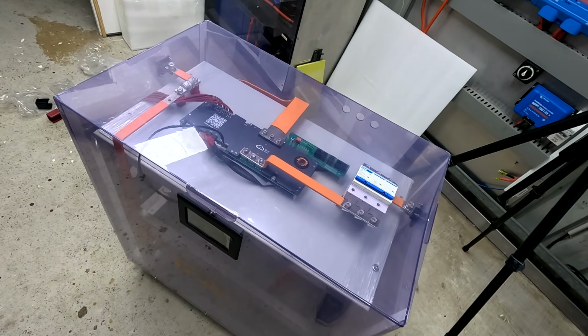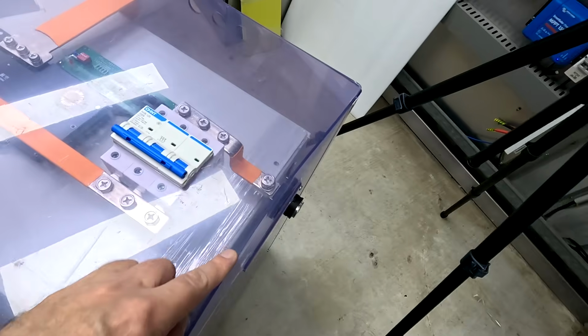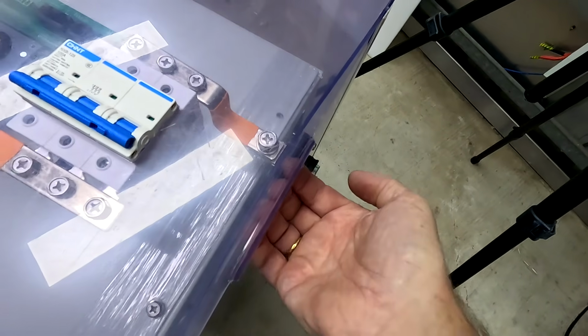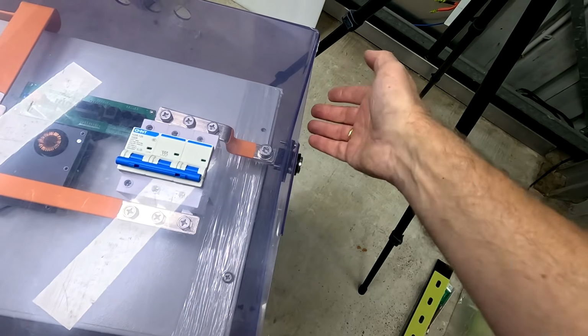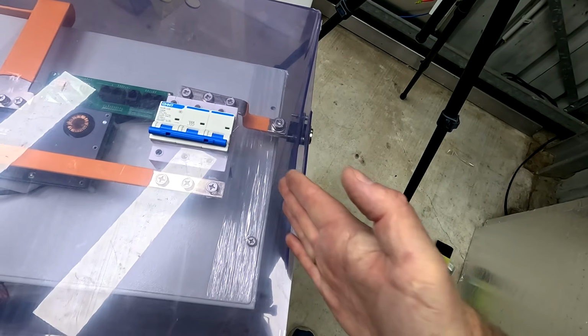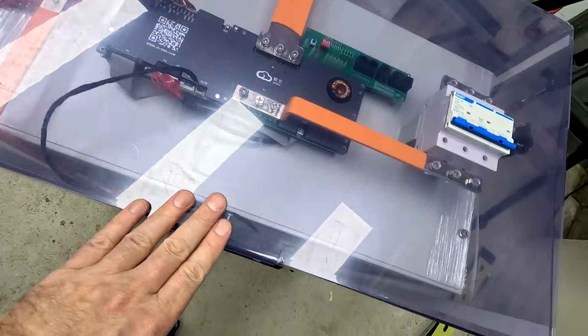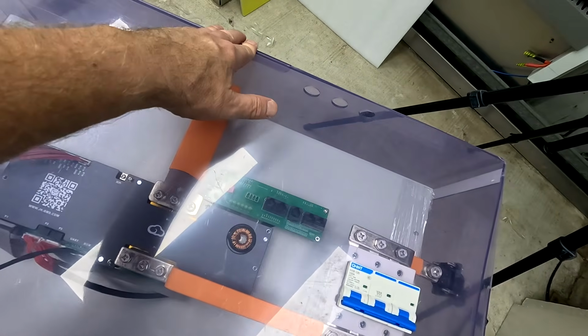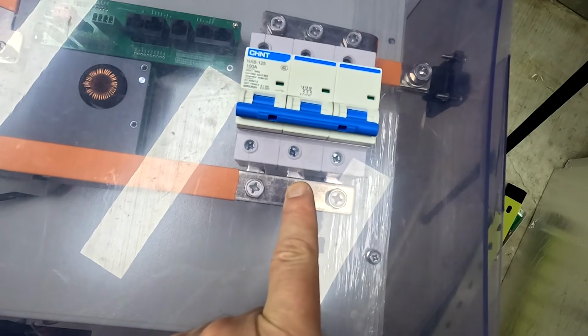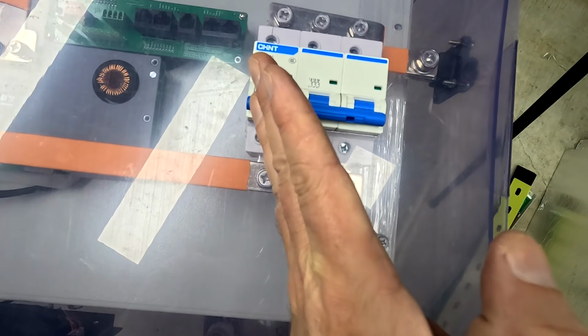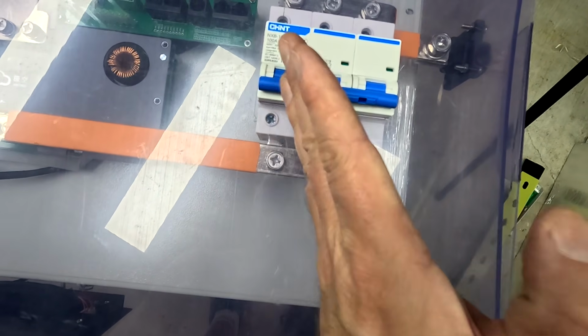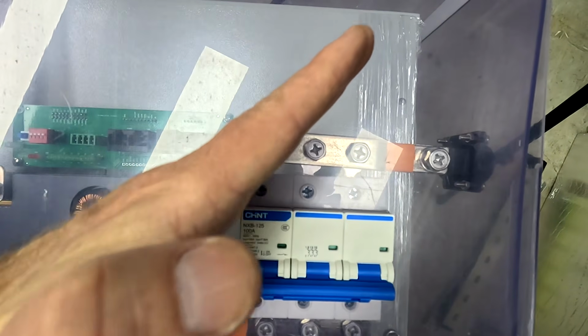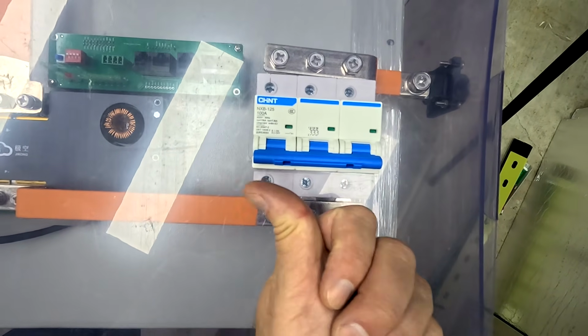So I'm trying now for a couple of minutes to get this lid on, and I'm unsuccessful - look at this gap. You can see how this side wall is bent inwards, how it curves. Front is cool, this side is cool, back is cool. And look how the links look from the bus bar to the breaker - they stand in this direction, same on this side, because the breaker needs to move over there to fit into this hole.